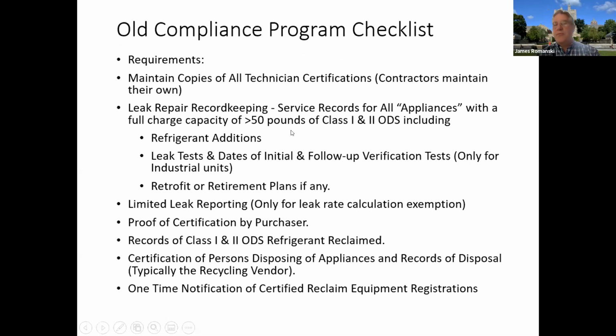Our policy was that every time somebody went out and did service on a unit, unless they were just changing a belt, anything that involved adding or taking out refrigerant, we asked them to assume we had to do a leak rate calculation. We might not get the paperwork until later and may be calculating the leak rate a bit later, so we might not find out we exceeded the leak rate right away. So we told them anytime you put in or take out refrigerant, assume it's going to blow the leak rate, even though most of the time it doesn't, and make sure you fill in all the information we need.